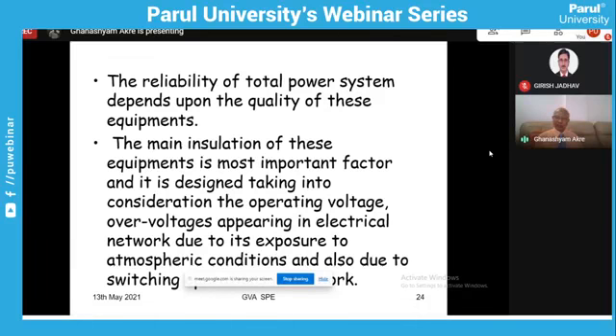It is very impulsive voltages. Similarly, it can have overloads because some feeders are drawing high currents because of their usage and all these things, so they are within 2 to 3 times maximum. But there will be switching surges coming in, when this is an inductive and capacitive circuit, the whole system. If you consider, then if any equipment is switched on or switched off, it produces surges.